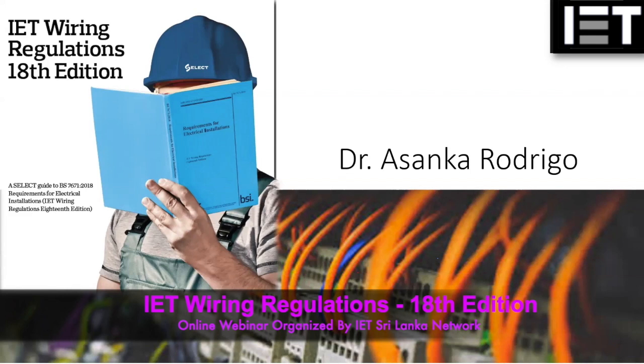Dr. Asanka, there was another question while you were discussing with Mr. Bandula. What is the size of the conductor used to connect metal doors and windows to the main earthing system? There is a table given in the IET Wiring Regulations, depending on the certain requirement. The equipotential bonding and the supplementary bonding minimum requirements are given in the standard. I cannot remember the exact values, but the person who asked can refer to it, and I can even share the table. There is a specific table for the minimum requirement for the cables.